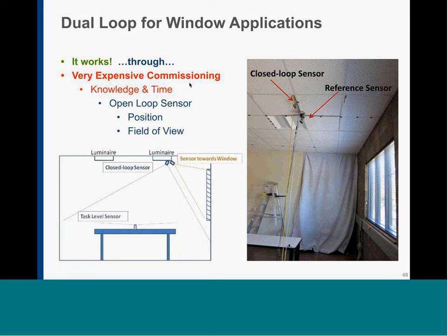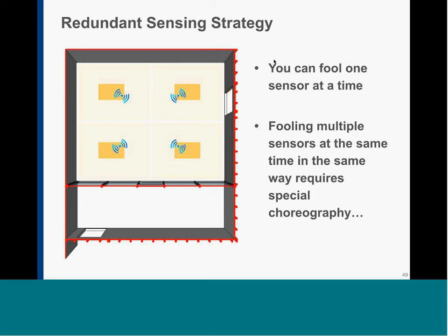Here you can see a schematic of a daylight harvesting laboratory at the California Lighting Technology Center, with a pretty large office space where we can split it in half and have 2 individual spaces or 1 open. And you see 4 luminaires with communication capabilities, and as you will see, each one carries its own sensors. Here we have an internal facade, and in this area, especially on this wall at the bottom, we have installed what we call the sky wall. The sky wall is a pretty large array of fluorescent lighting that was available at the time. If we were to do it today, we would use LEDs, but it works pretty well.